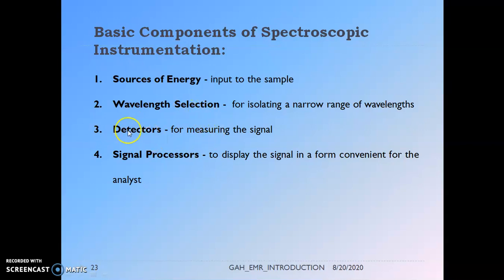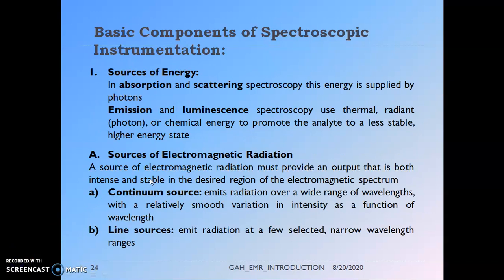Detectors measure the signal coming out of the sample cell, pursuing those signals and converting them into electronic signals. Signal processors take the electrical energy and put it into a convenient form for observation and analysis. In absorption and scattering spectroscopy, energy is supplied by photons; in emission and luminescence spectroscopy, thermal, radiant, or chemical energy is used to promote the analyte to a less stable, higher energy state. Any electromagnetic source must provide output that is both intense and stable in the desired wavelength region.